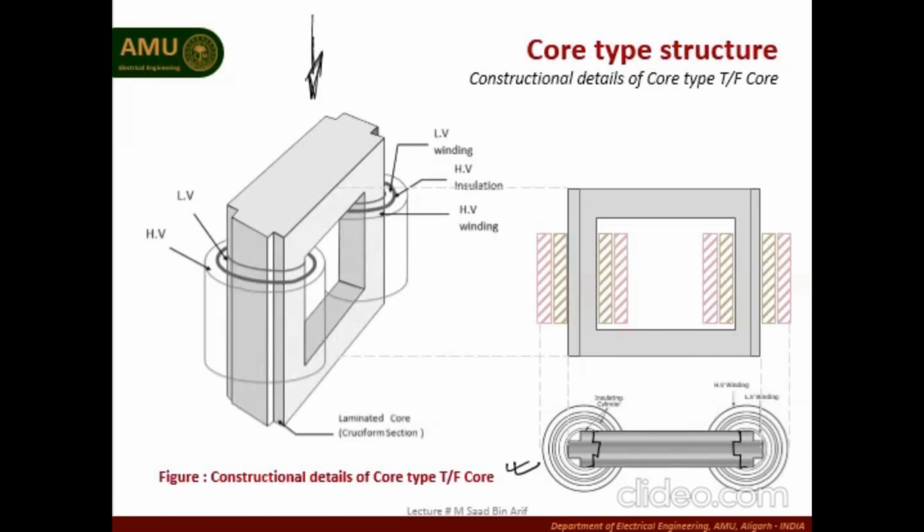It is due to this reason that the stepped core construction becomes mandatory for the core of a large transformer. In this figure, you can see a typical stepped core construction. When the core size increases, it becomes very difficult to cool the core, and for this purpose, cooling ducts have to be provided in the core in order to reduce the temperature of the core.